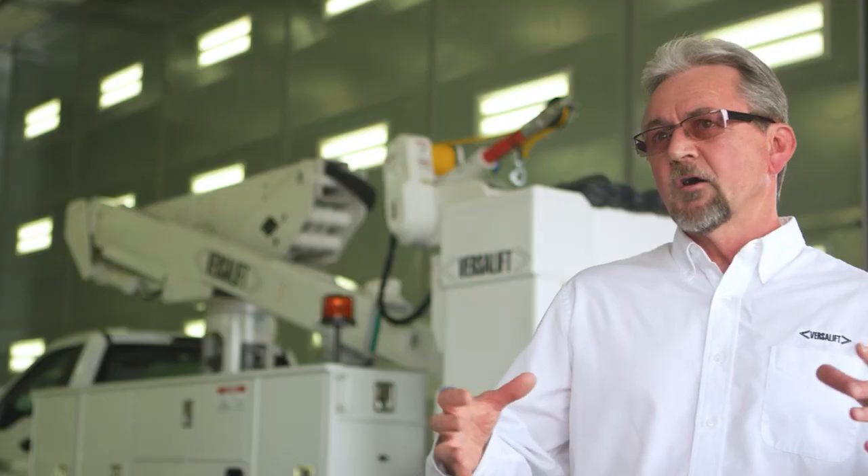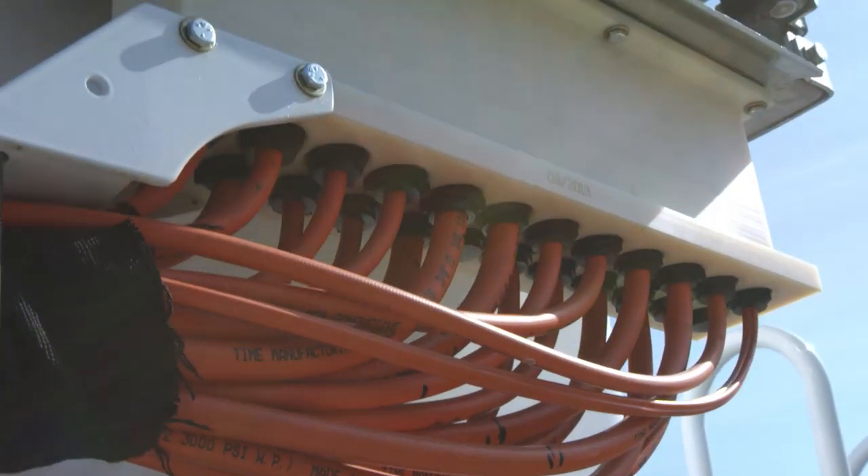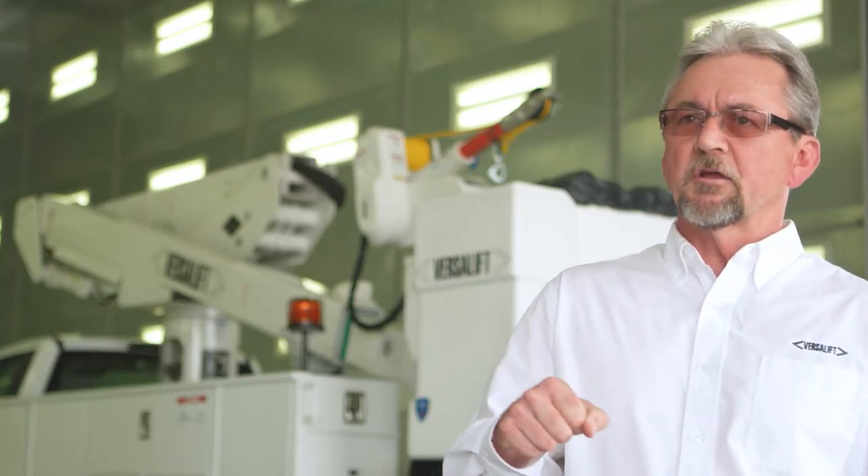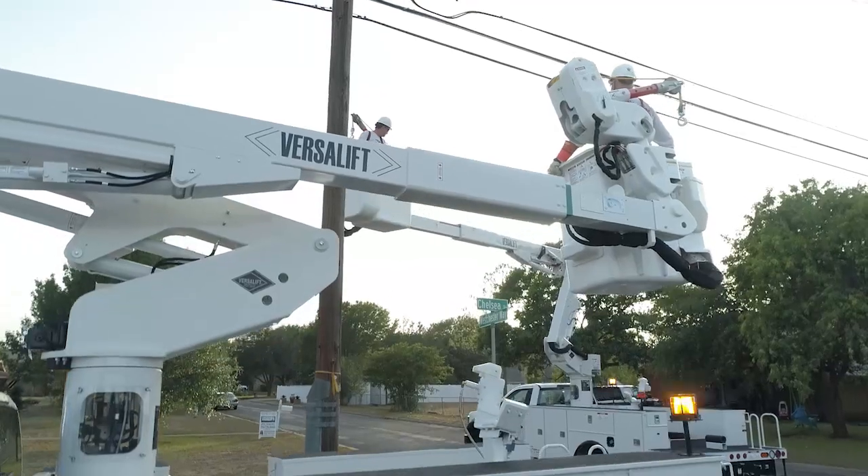The TruGuard system is protected underneath the valve and all the components, as well as behind a bubble cover. We do have insulated hoses — they're non-conductive — but each one of those hoses is a place where contamination can land. In the hose bundles, that contamination gets in between the hoses and isn't easily washed out. So while the hose itself may be non-conductive, it's the contamination getting on them that makes them no longer non-conductive.